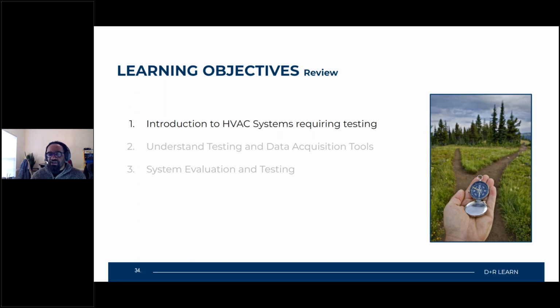I think they're looking to try to go away from the use of absorption chillers. If I'm not mistaken, I could have sworn I read an article about that somewhere. I will look for it. That's the second thing that I need to write in here. The first one is the heat recovery option instead of utilizing actual natural gas, or you do have heat pump options now, where heat pumps today are much better than they were 20 years ago.